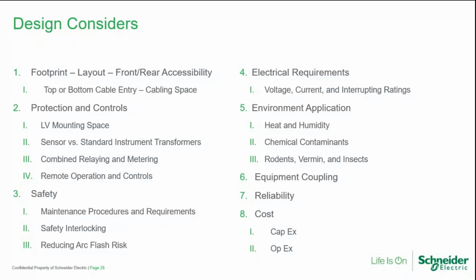Am I designing for a customer that has qualified MV electricians on site who will be able to maintain their switchgear on a regular basis as it should be maintained? Or is this customer basically already treating their switchgear like set it and forget it, like we find a lot of our customers are already doing? If that's the case, maybe I should consider giving them a longer maintenance cycle style of switchgear, a more reliable design of switchgear. So all good considerations, questions to ask yourself when you're going into a design phase with medium voltage switchgear.